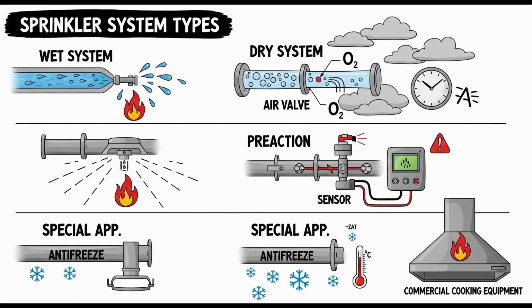No shortcuts. Yes. If there is a sprinkler head located within the dry pipe valve enclosure, which is often done for fire protection of the room itself, its water supply can come from the dry side of the system. Meaning it only gets water when the main valve trips. Right. Or its supply can come from a separate wet pipe system, specifically protecting that room. Providing redundancy for protecting the vital valve area. Smart. Very. The source also mentions protecting against a high water level for some dry pipe valves.